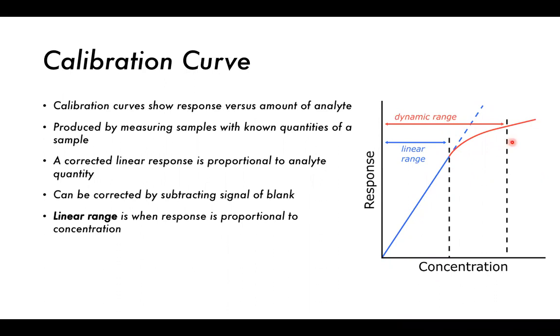So this is still, as I've said, measurable to the instrument. However, this measurement is now complicated because of various factors, but usually the biggest factor is that the analyte is now interacting with itself. Previously, whenever it's in low concentration, the analyte molecules or atoms or whatever they happen to be are sufficiently far away from each other, sufficiently separated that they don't actually interact with each other. But as the concentration increases, it increases the chance that the analyte will come in contact with other analyte molecules. And this can cause changes in the instrument response, because there are new pathways of relaxation. A lot of these measurements rely on the idea that something is going to be absorbed or some energy transfer is going to happen to our sample. So whenever the analytes can interact with each other, they can cause new pathways for relaxation.